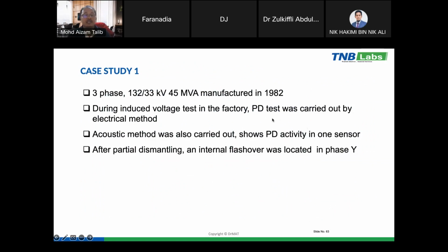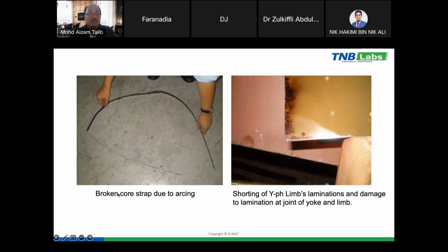Okay, on the case study, one of the successful case studies on the PD measurement on power transformers. This is a 132 kV power transformer during the induced voltage test in the factory. We also carried out the PD testing by electrical methods, but it failed. So we put acoustic sensors on the transformer. Only one sensor was active. Since the transformer was already in the factory, we opened the transformer, and finally we were able to find the root cause. We found an internal flashover located at the Y phase of the windings here. You can see this broken strap due to this arcing, and then shorting of Y phase of limb laminations between the joint of a yoke and limbs.